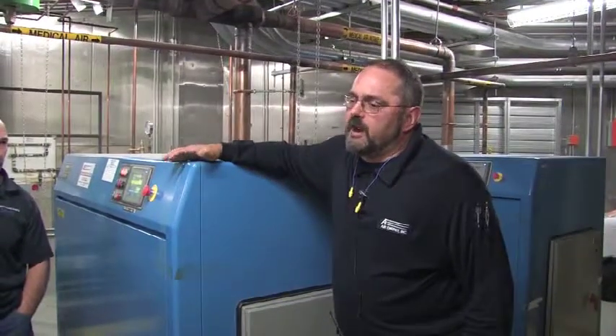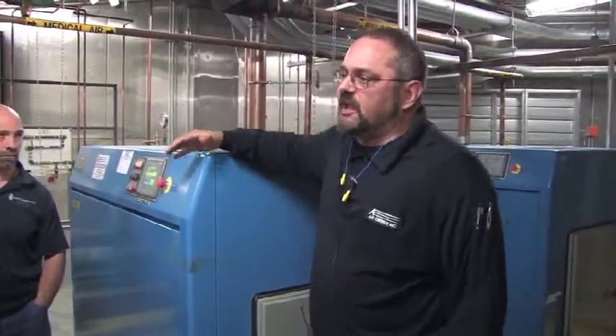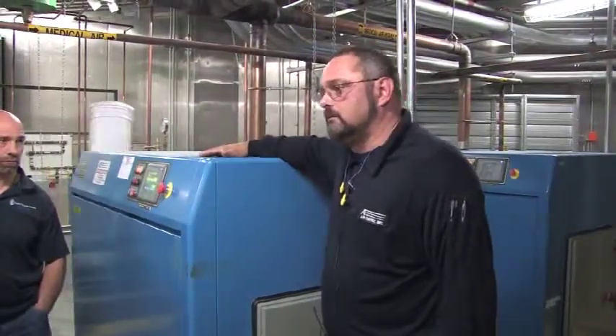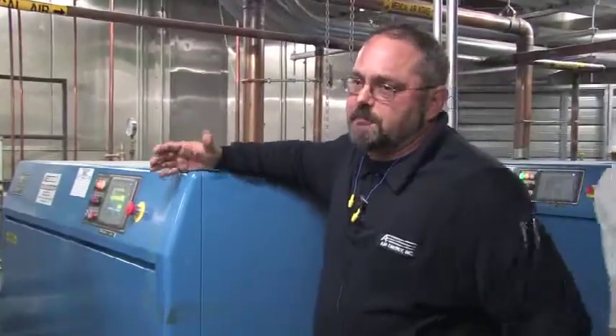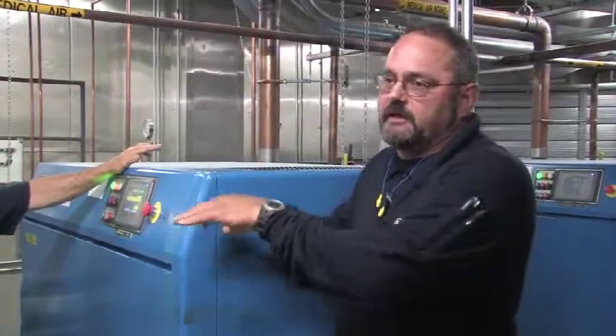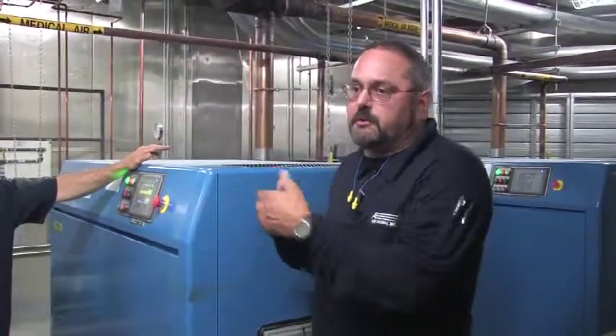And the programming is interesting from the standpoint of all 3 machines have the same basic program to operate the unit. The sequencing program is actually a separate subroutine that's called up. So the software for that is running on the same Allen Bradley PLC, but it is literally not connected with the operating software for the machine, if you follow. Basically what the programming does is substitute new values for the load and unload or start and stops in the existing software that operates the machine. That's really the only connection. So the sequencer portion of the program is totally separate. So if something goes wrong with the sequencer, you can literally take the machines out of sequence and run them as normal machines in local mode.